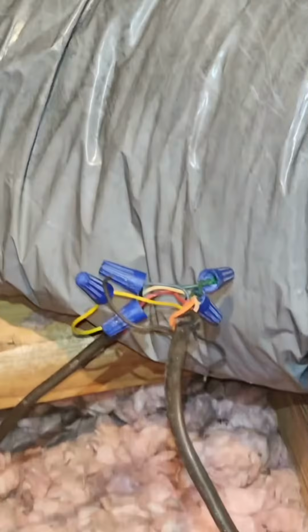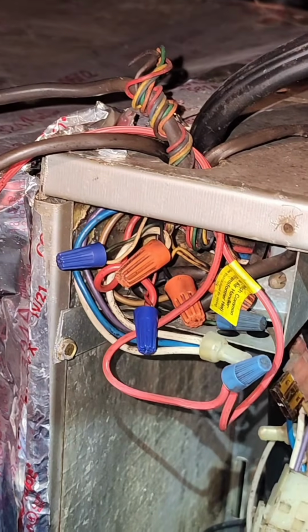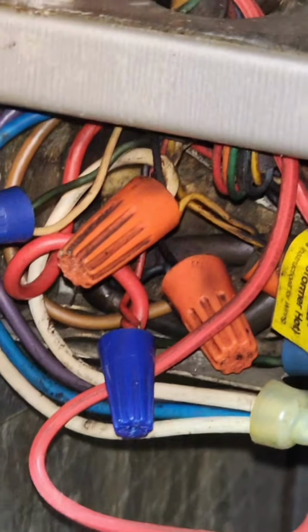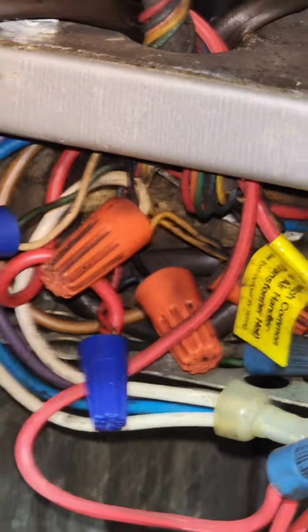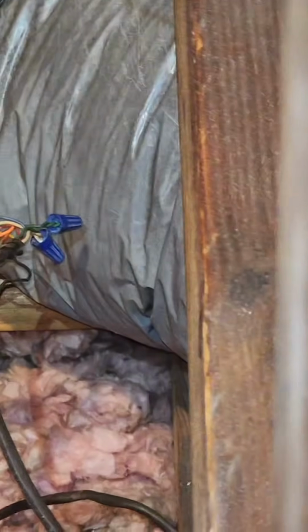So they must have pulled a new wire for whatever reason. But I use the blue common wire as orange for the reversing valve. So I just gotta see how it's wired up over here, so everything will work properly. So that orange wire right there, I'm gonna have to connect two over here to the blue wire. And we got batteries in the thermostat for the common.